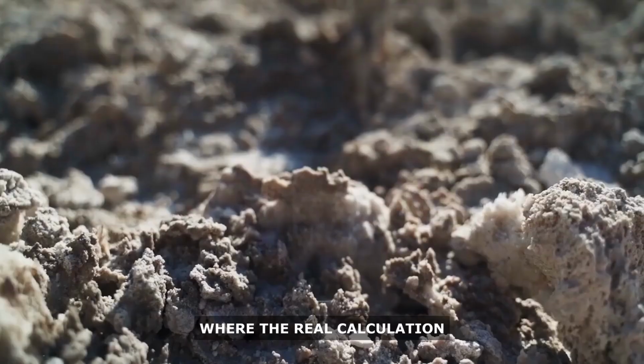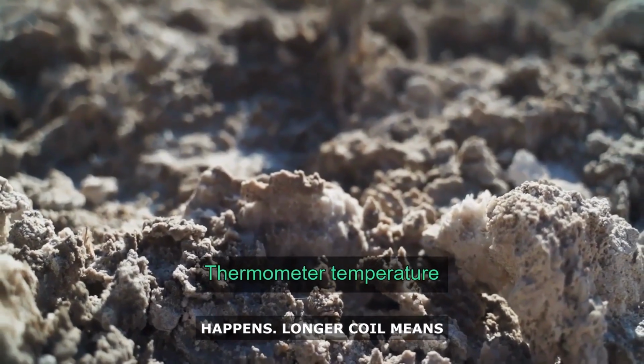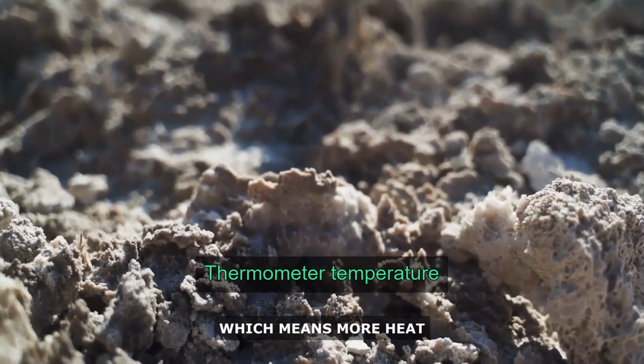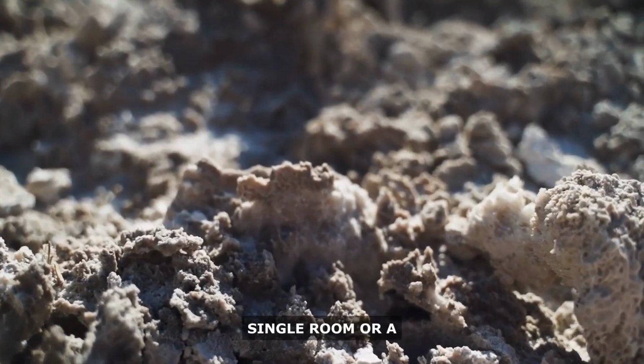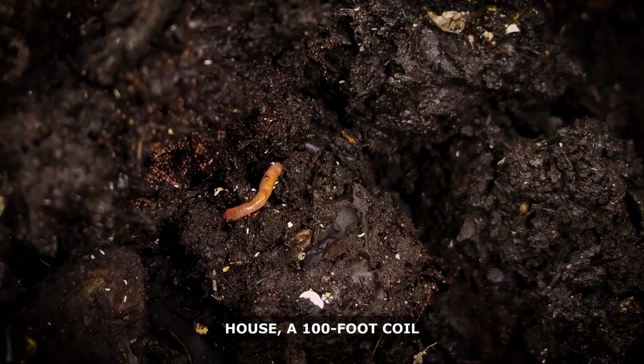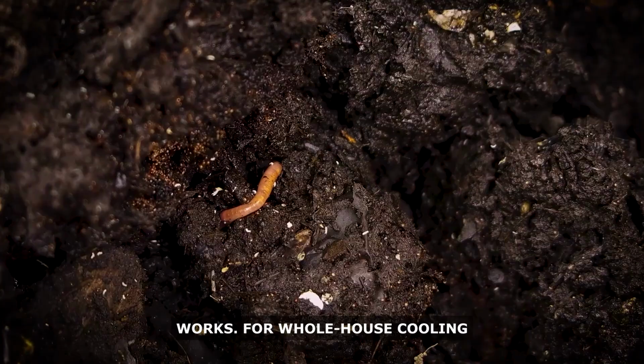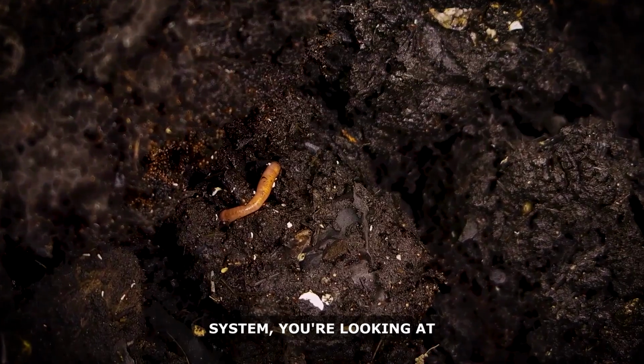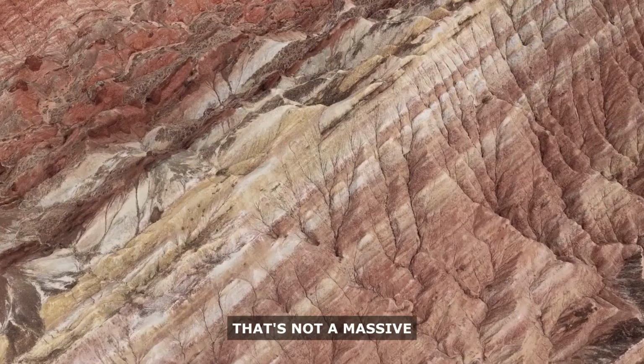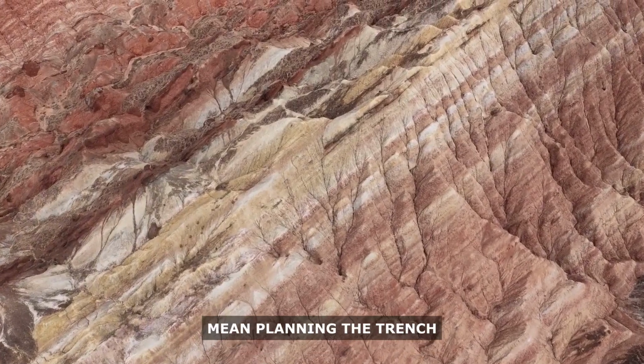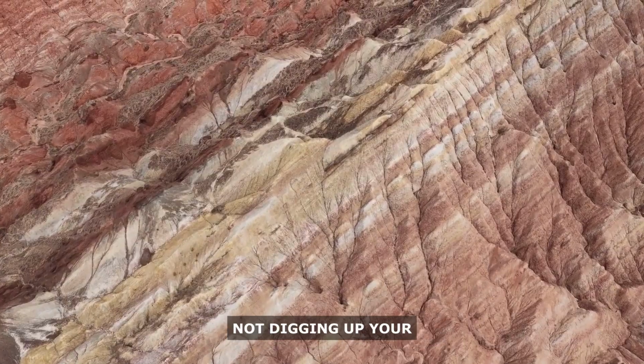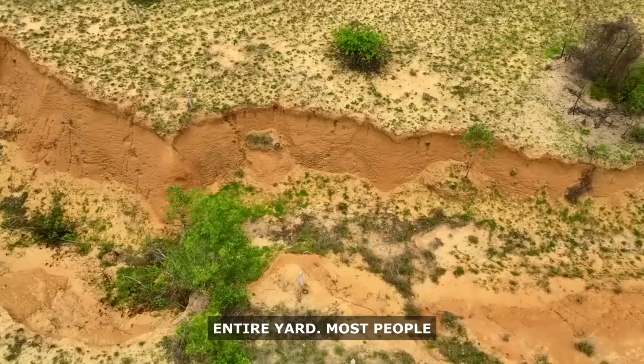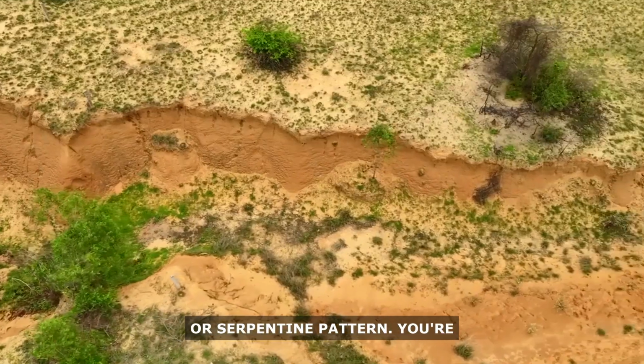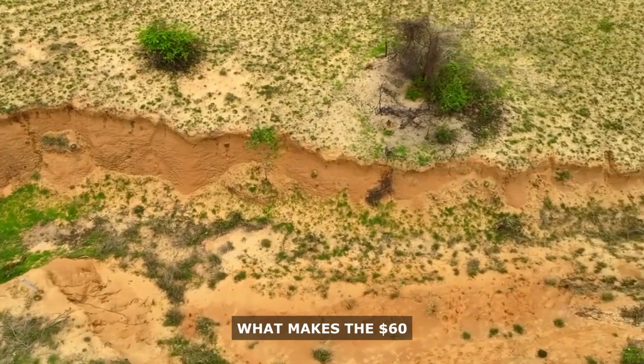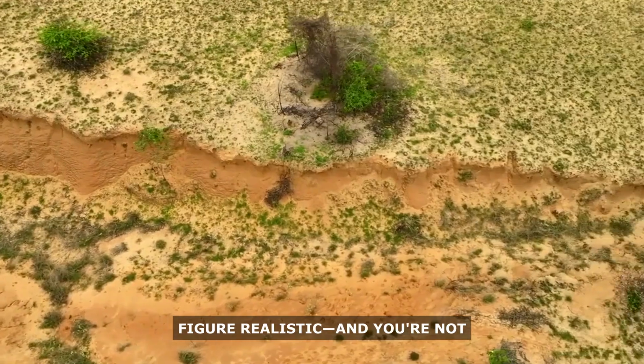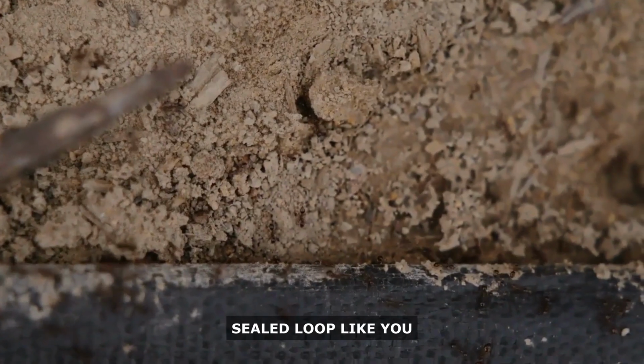For whole house cooling through a central duct system, you're looking at 300 to 500 feet. That's not a massive undertaking, but it does mean planning the trench route carefully so you're not digging up your entire yard. Most people do a simple spiral or serpentine pattern. You're burying copper tubing, which is what makes the $60 figure realistic, and you're not worrying about a perfectly sealed loop like you would with a geothermal heat pump. Water goes down one side of the buried coil, absorbs heat from the earth, and comes back up the other side. That's it. The physics is passive and elegant. It requires almost no power to work.